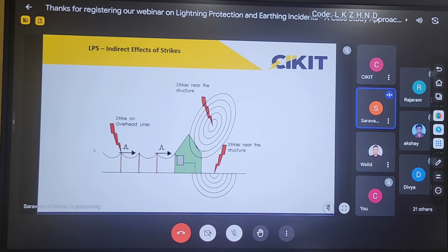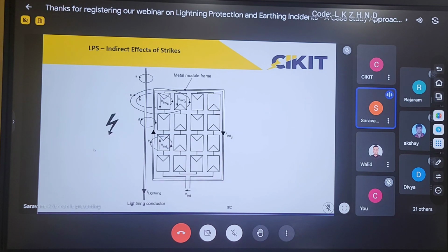Even if the lightning is striking somewhere away from the building, the electronic equipment inside the building may get damaged. So if I want to provide protection, I have to provide suitable surge protection devices. Here you can observe that the first one is the lightning conductor. If I have a lightning conductor and, instead of these panels, any power line or data line, then obviously the magnetic field produced will have an impact on this power line or data line.